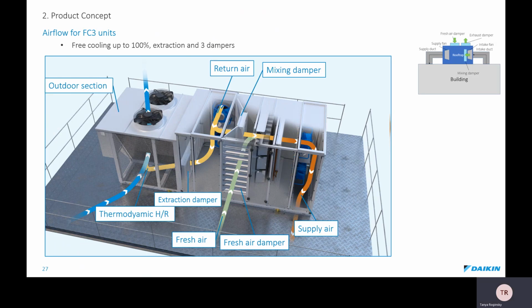Next is FC3 units. The FC3 unit configuration has a 3-damper arrangement and an extraction fan. The arrangement is different from FC2, where we only have supply fans and there is an overpressure in the building. With the FC3 version, if we have, for example, 30% fresh air added to the return air, which is 70%, we will also have to extract 30% of the air in the building to keep the pressure balance in the building.